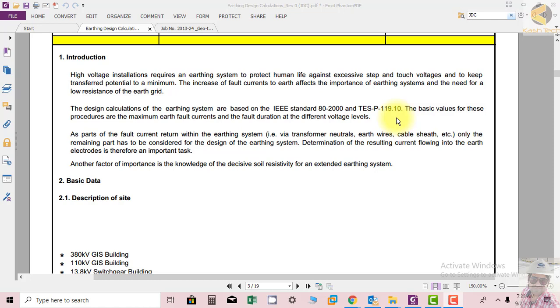So what does 3 seconds mean? I was in one of the meetings on design calculations. If you see the conductor specification provided by the manufacturer, they will also provide the short circuit rating, the short time rating, for the conductors. If huge current flows through the conductor and it is more than the capacity of the conductor, the conductor will heat up and it can melt down, it can evaporate in the air. So the conductor cannot bear the current beyond this provided short time rating unless it damages itself. So it is most important.